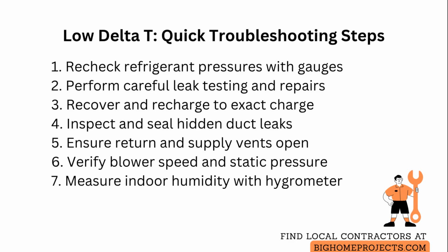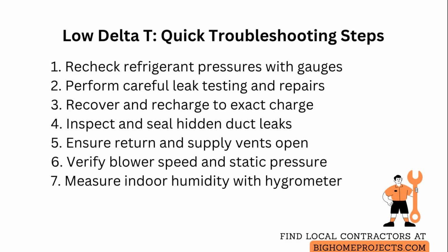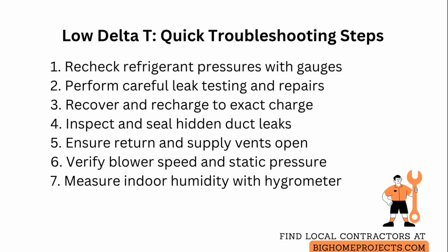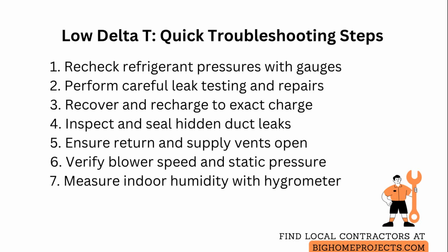Make sure return and supply vents are fully open and unobstructed, and verify blower motor speed is correct by observing static pressure or listening for abnormal sounds. An underperforming blower reduces coil delta T.